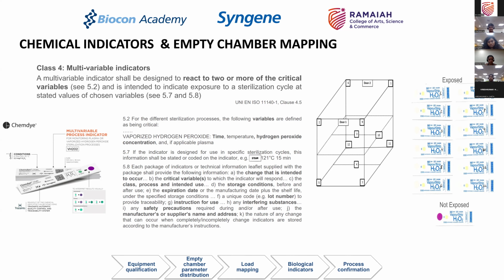So you will place them at different locations. You can see it is placed on the four corners of each side. Then it is placed in the middle, in the center of the chamber. And based on this, one will be at the front, one will be at the back, the different positions where they are placed. And then the vapor cycle is run.